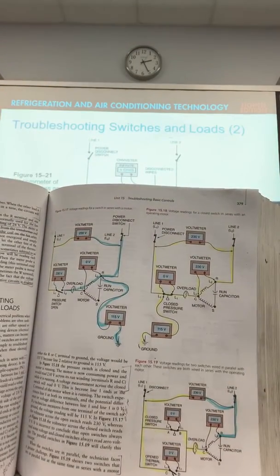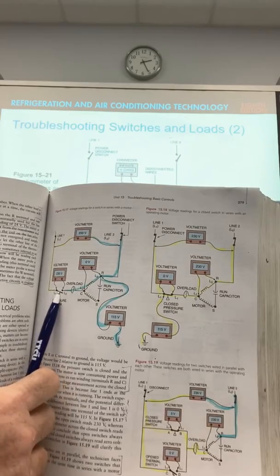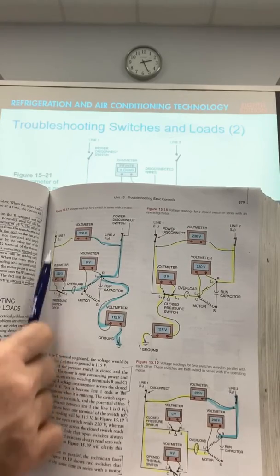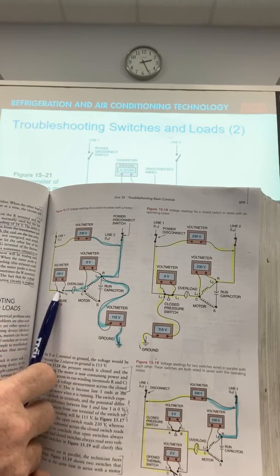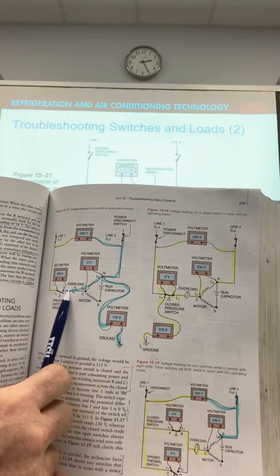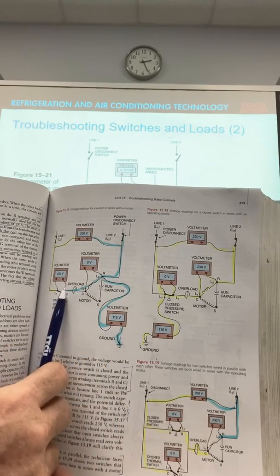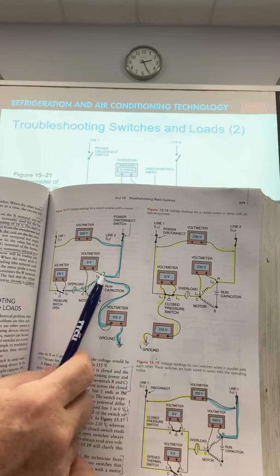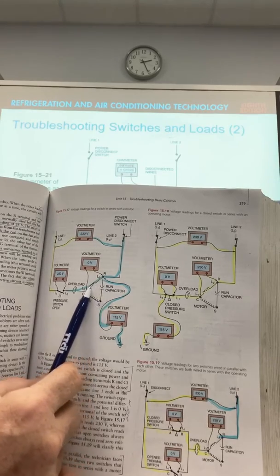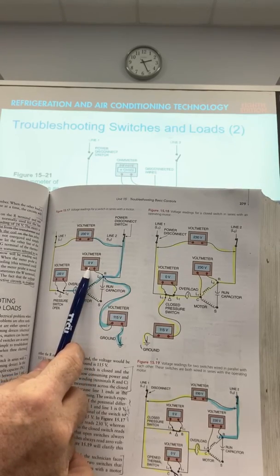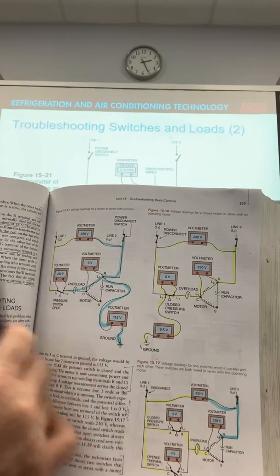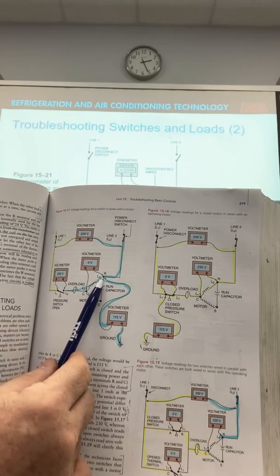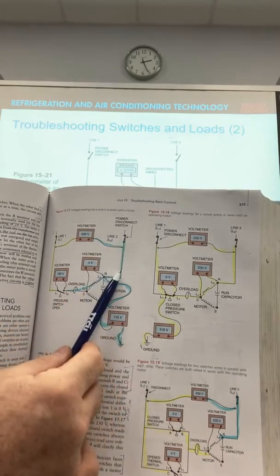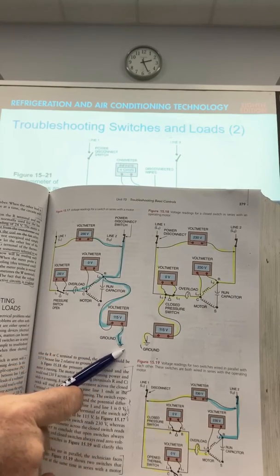Notice here with the switch open. I'm on this leg here, and the power is feeding through here, so I got 230 volts. Across a closed winding, I'm on this side of the circuit, I got 0 volts. One side of this leg, which is 115, the ground is showing me 115.